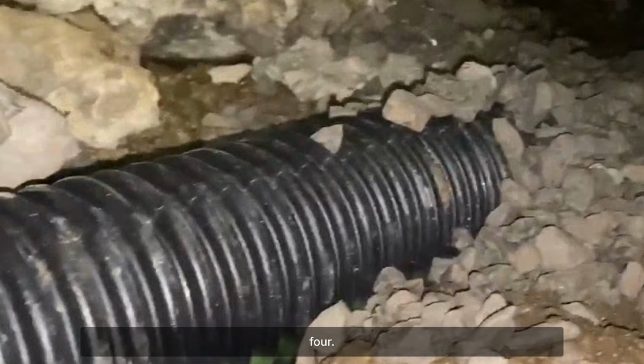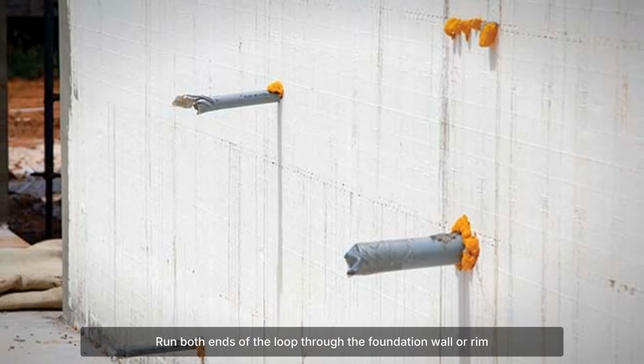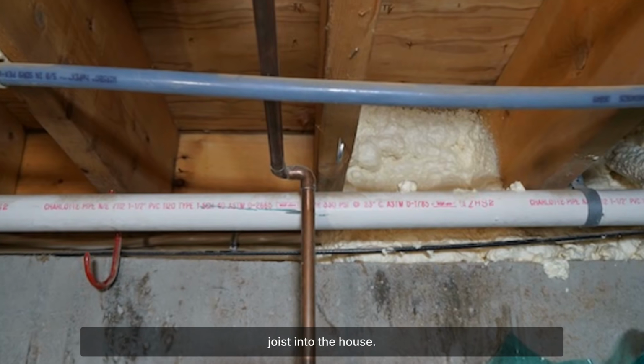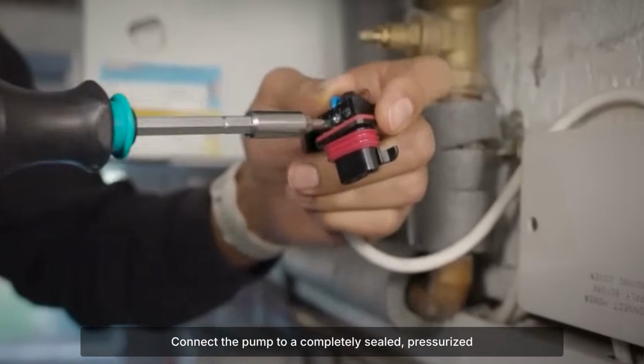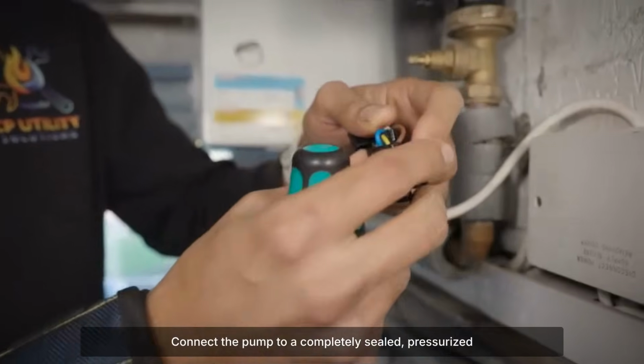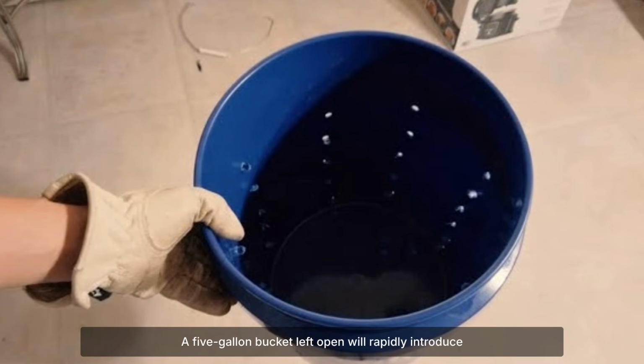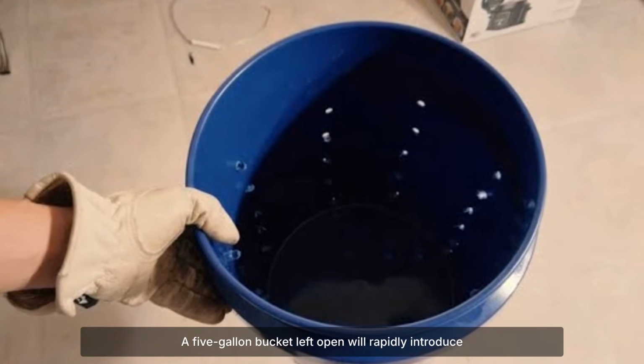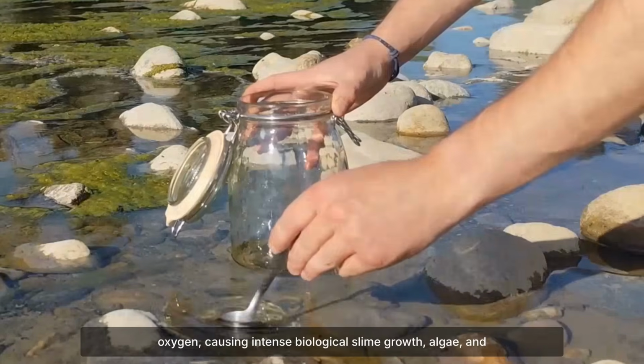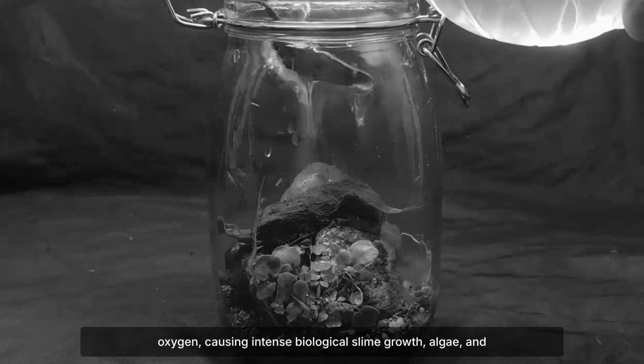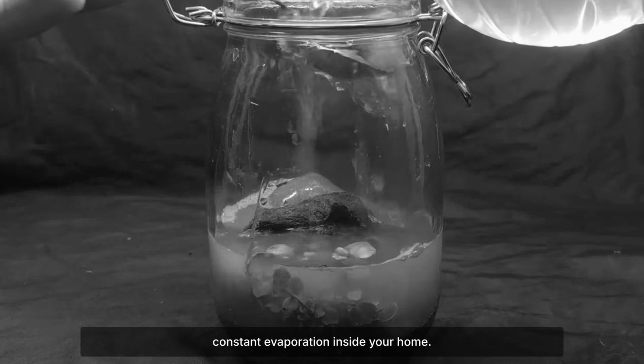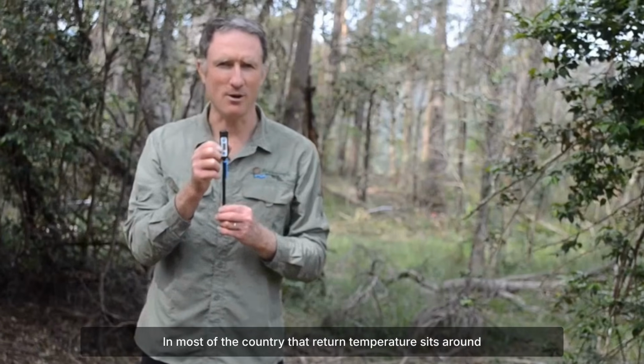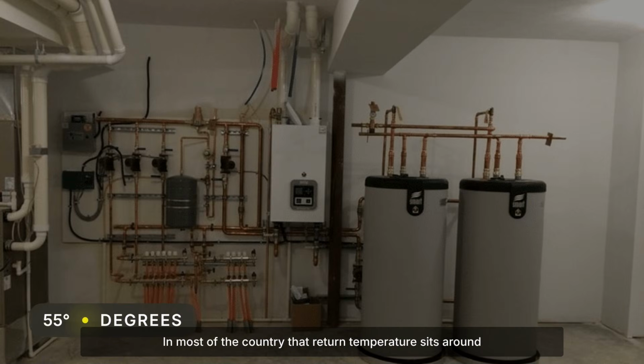Damp earth pressed tight against the pipe conducts heat away far more efficiently than loose fill or aggregate. Step 4. Run both ends of the loop through the foundation wall or rim joist into the house. Connect the pump to a completely sealed pressurized hydronic loop. A 5-gallon bucket left open will rapidly introduce oxygen, causing intense biological slime growth, algae, and constant evaporation inside your home. In most of the country, that return temperature sits around 55 degrees in the dead of July.